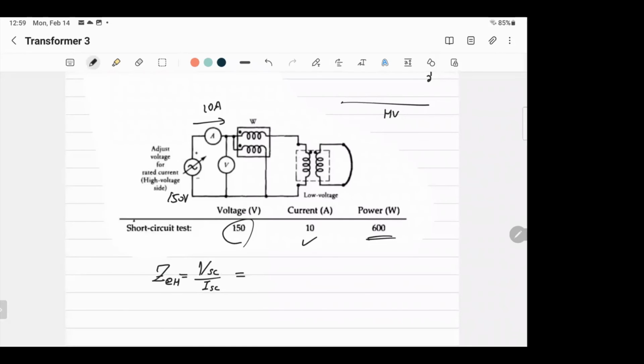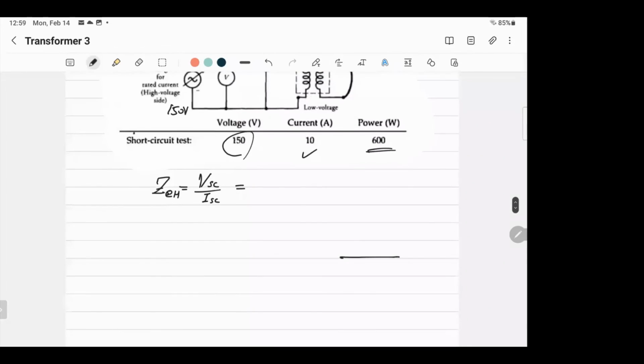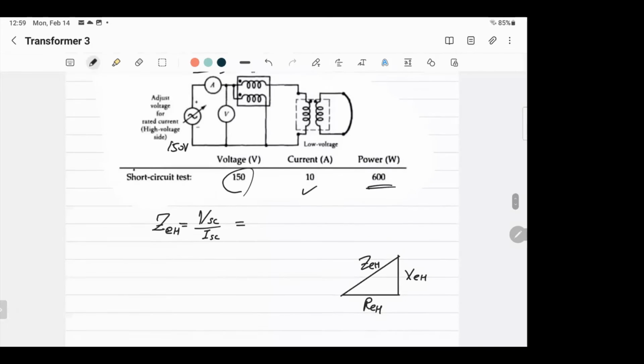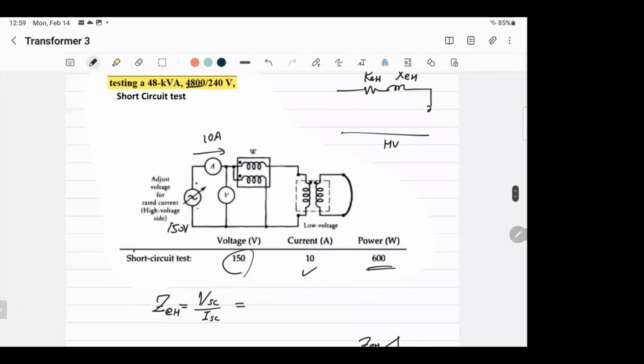You know that's the resistance, that's the inductance, and that's the impedance — R equivalent H and X equivalent H. Dividing the voltage by the current gives the whole impedance referred to that side, since that's the voltage applied and that's the current measured, and remember this is a short circuit, so the voltage across these two points equals the voltage across that impedance. Dividing 150 by 10 gives 15 ohms.